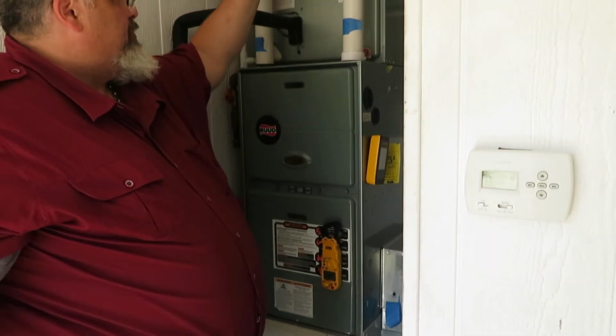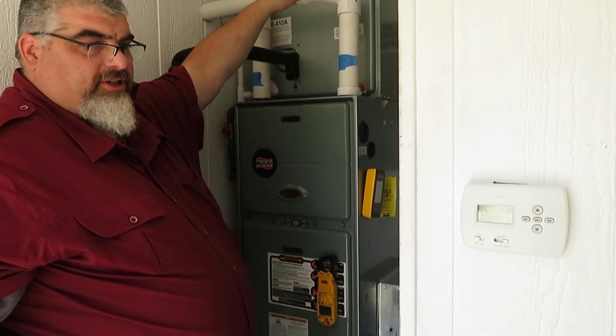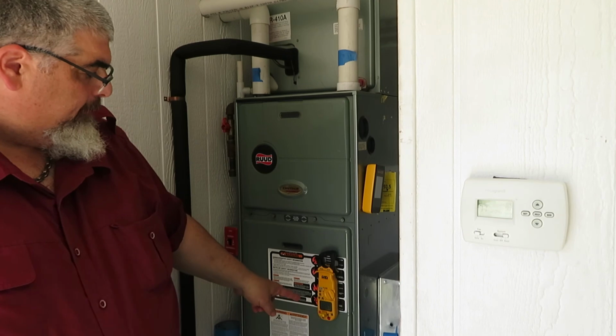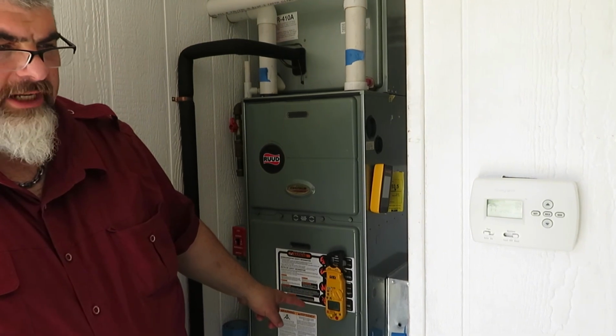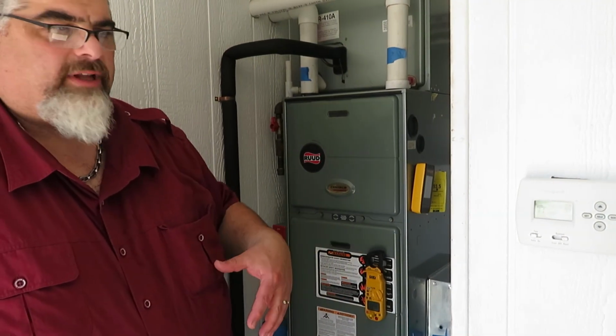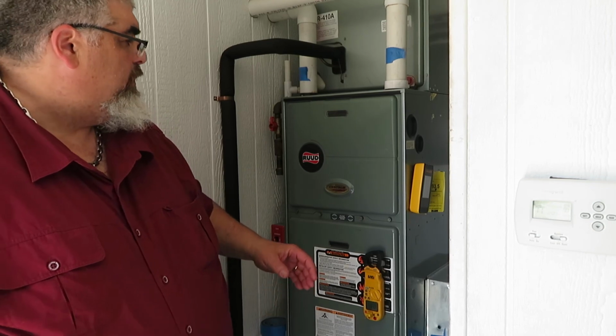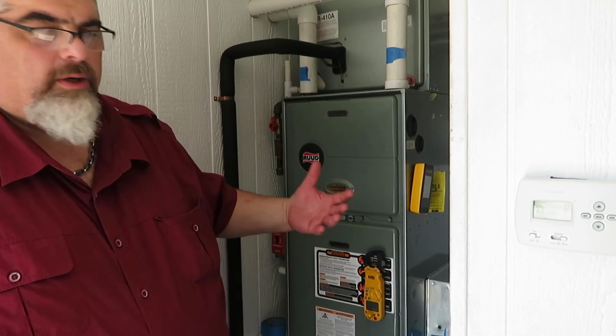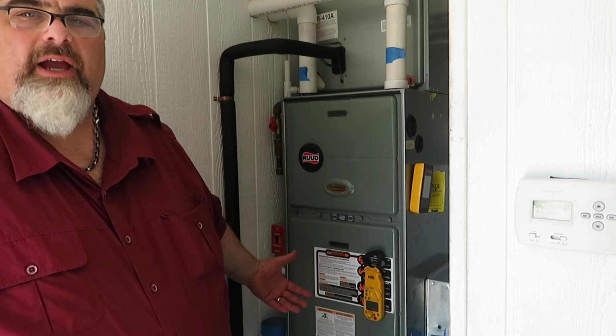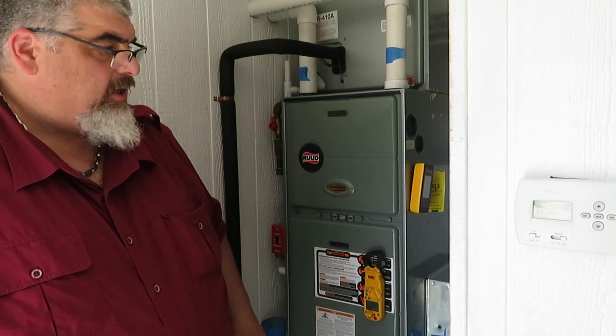So we're going to take the temperature from the supply, which was 160, subtract the return, which was 92.5, and that gives us our temperature difference. And as long as we're within 40 to 70 degrees, we're good. And that is basically how you conduct the temperature rise on a furnace.